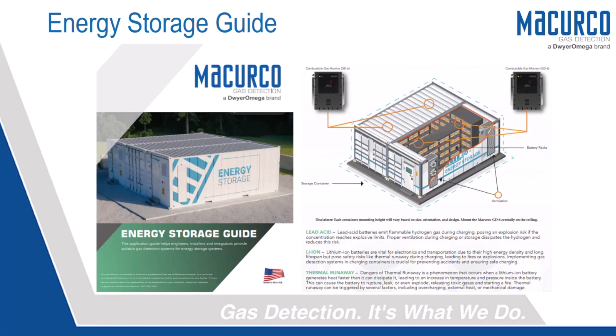Within that same application guide, you'll get a breakdown. Pay attention that hydrogen is the main runner. You'll see that under combustible gases, but you're also going to see carbon monoxide, we're seeing a big push in CO within these spaces as well. So you throw it all back to a big system, whether that's a BMS, a fire panel, or a Macurco gas detection panel, it doesn't matter. At the end of the day, we're looking for a big system out of these data centers and BESS containers. You're looking at one or two sensors per container, and there are tens of thousands of these out there, so a big push in that battery storage space.